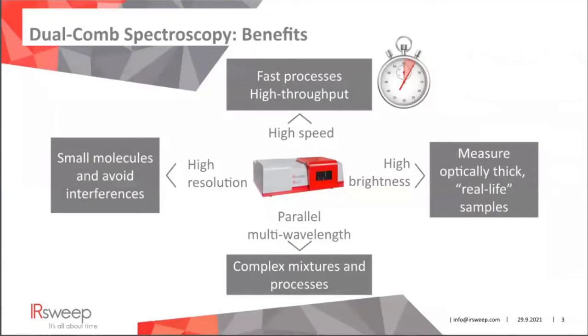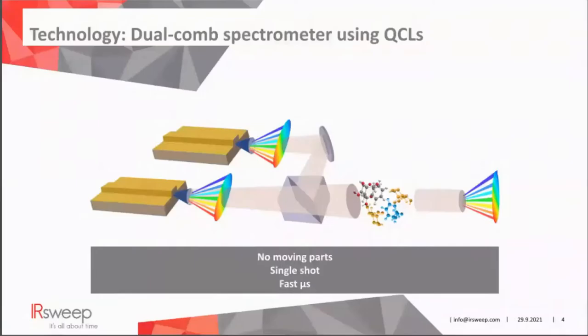There are several benefits of quantum cascade laser frequency combs. One is the speed advantage, with high time resolutions on the order of microseconds. Another is brightness — the dual-comb spectrometer uses laser sources that are orders of magnitude stronger than thermal light sources. Additionally, complex mixtures can be identified and monitored as several laser lines are recorded. Last but not least, there is a high-resolution version, the Iris F1, which allows recording at one milli-wavenumber resolution or better in a few minutes.